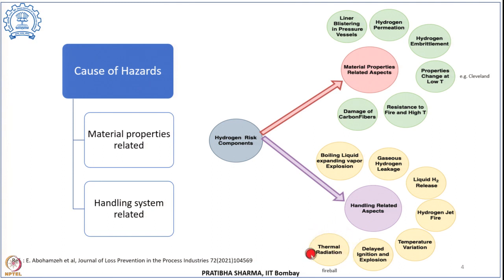Thermal radiation — from a high temperature flame or fire nearby — can lead to catastrophic events, causing damage to equipment and the structure of hydrogen facilities. This thermal radiation or high temperature can lead to loss of confinement in a compressed gaseous hydrogen vessel or liquid hydrogen vessel. In a compressed gaseous hydrogen vessel, the increase in temperature causes expansion that can lead to rupture of the vessel.